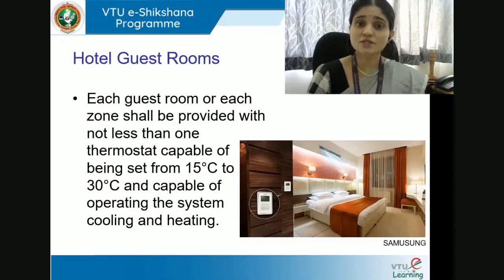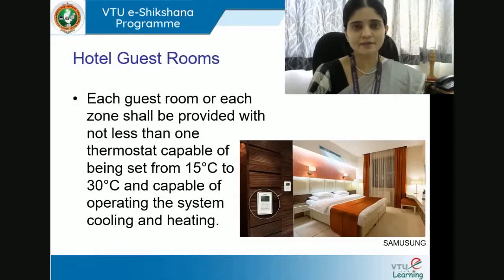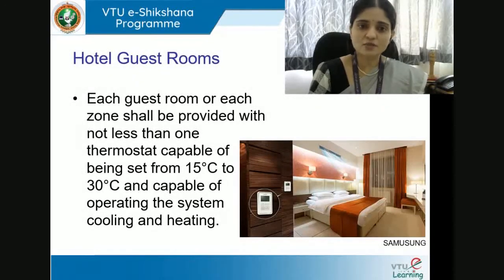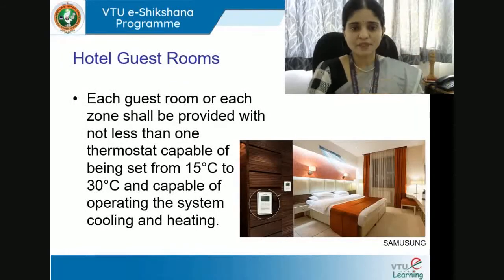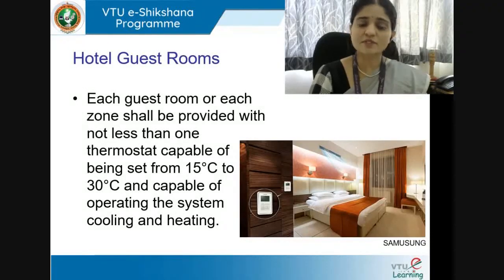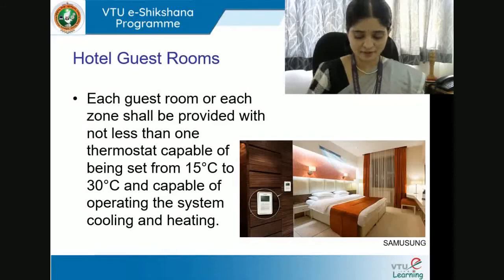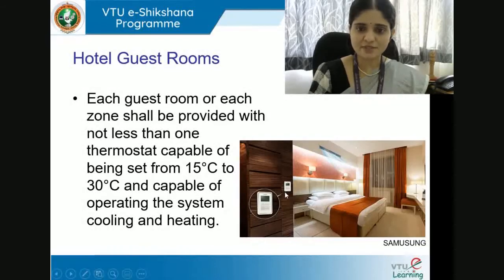Each guest room or zone — a zone being a group of guest rooms with similar HVAC calibrations — shall be provided with not less than one thermostat capable of being set between 15°C and 30°C, and capable of operating the system with respect to both cooling and heating. The thermostat is normally located on the wall.